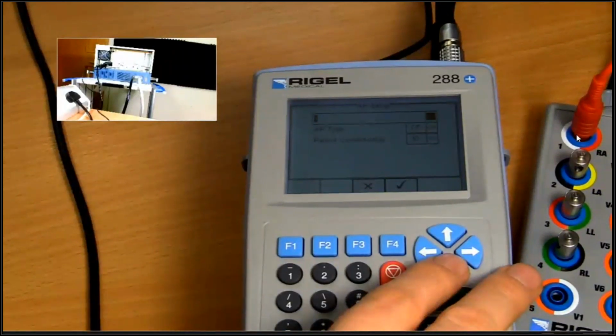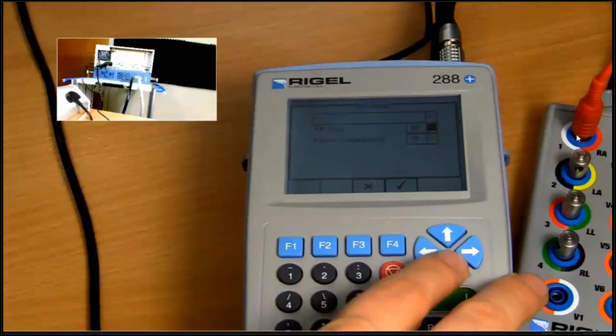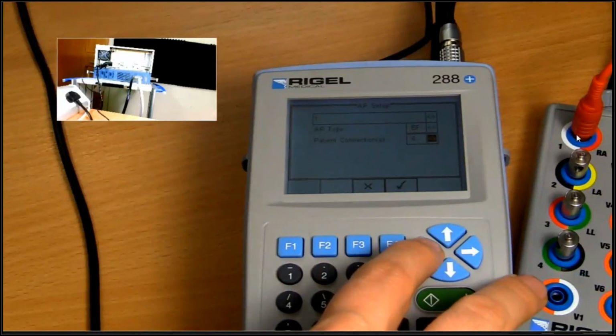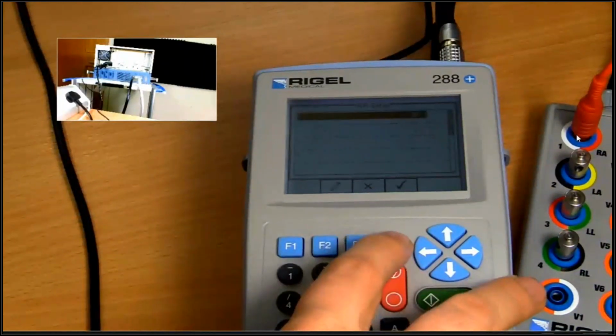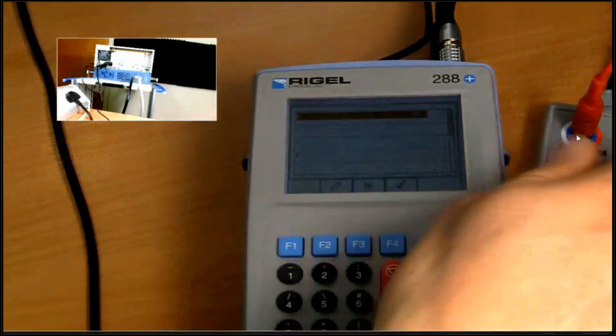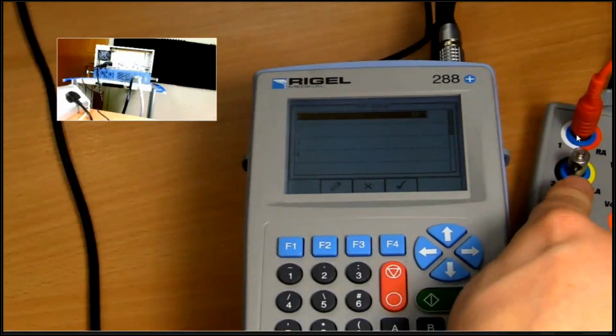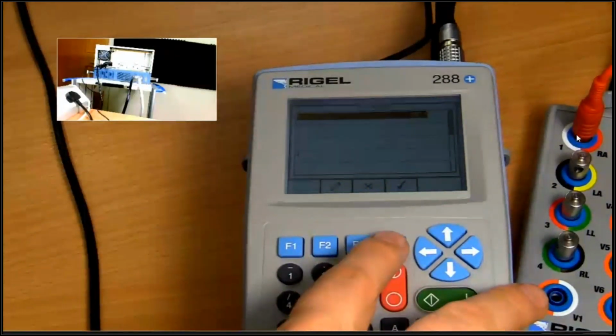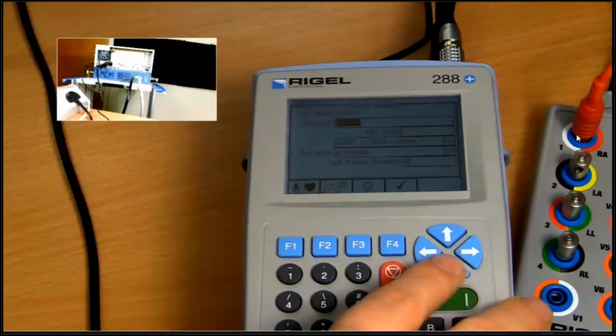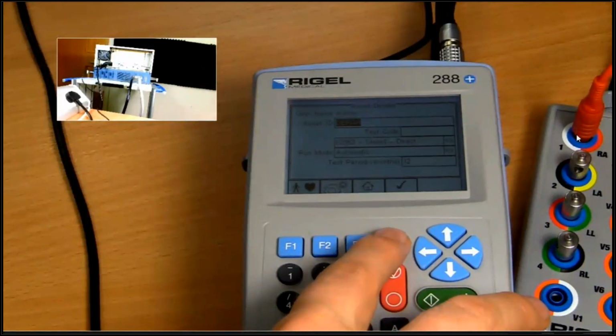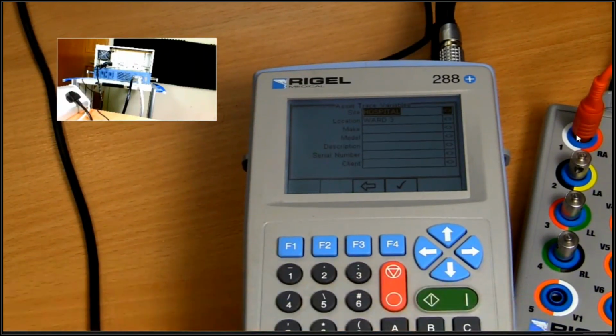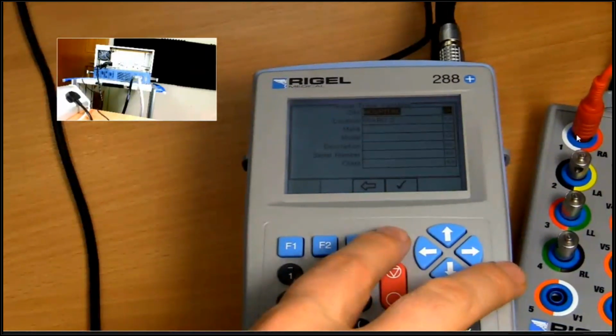And I've got, it's type BF, and I'm going to have 1 applied part, 1 patient connection. That'll be highlighted here. If I'm testing something like a defib, I can select CF, BF on different applied parts within this menu structure. So I'm quite happy with that. I'm just going to press F4. And then I've got a number of characteristics I can put in there. I can put in for traceability purposes, the site, location, make, model, description, serial number, this type of thing. I'm just going to leave this as default just for the purposes of this exercise.